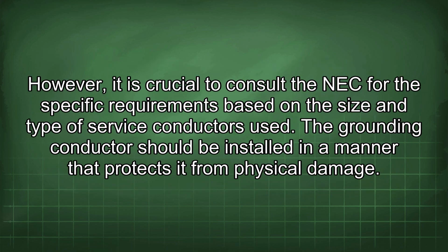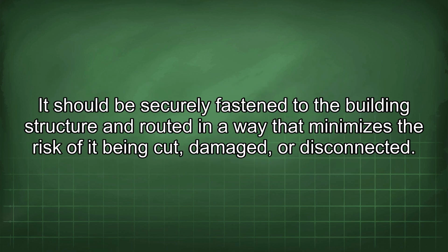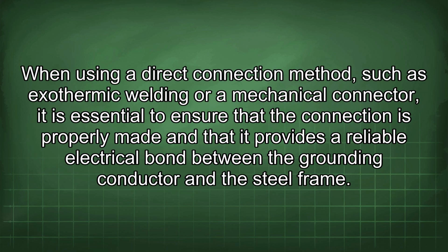However, it is crucial to consult the NEC for the specific requirements based on the size and type of service conductors used. The grounding conductor should be installed in a manner that protects it from physical damage. It should be securely fastened to the building structure and routed in a way that minimizes the risk of it being cut, damaged, or disconnected. When using a direct connection method, such as exothermic welding or a mechanical connector, it is essential to ensure that the connection is properly made and that it provides a reliable electrical bond between the grounding conductor and the steel frame.